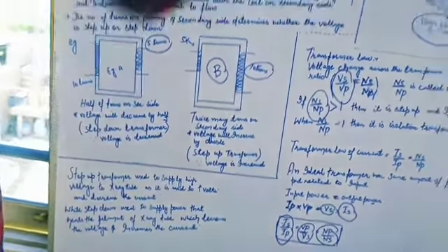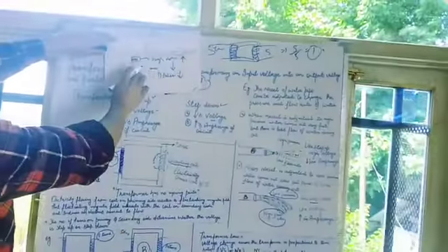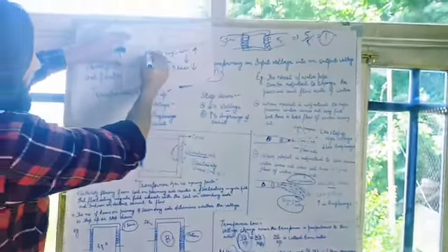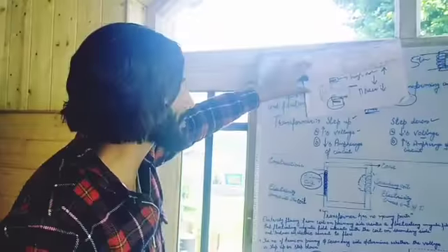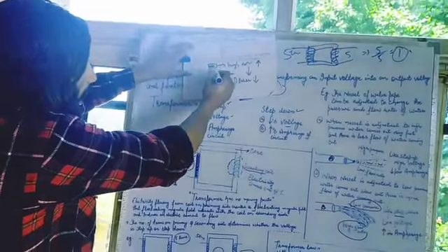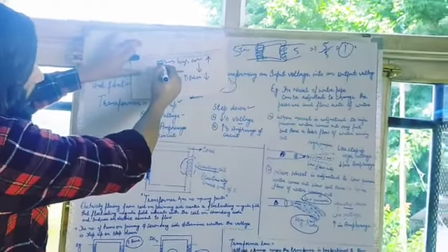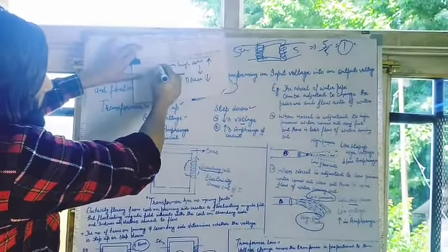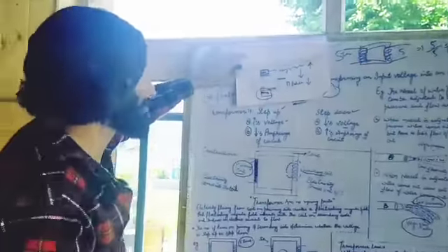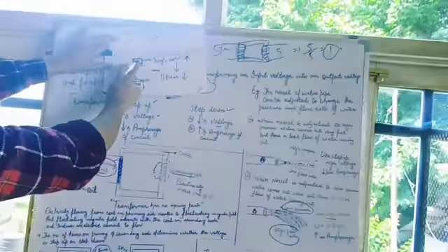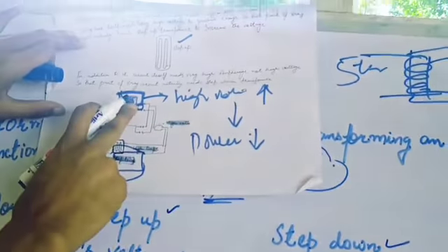Different parts of the X-ray circuit actually need different amps. The X-ray tube itself needs very high voltage to produce X-rays, so there is a need for the step up transformer to increase the voltage. Here we have the step up transformer on this side to produce the high voltage for the X-ray tube.